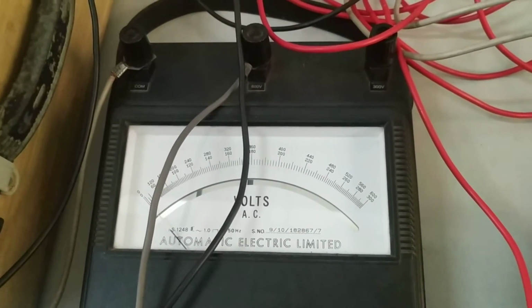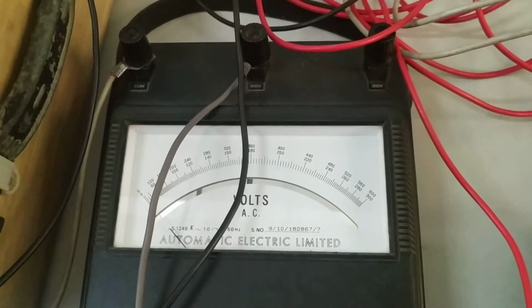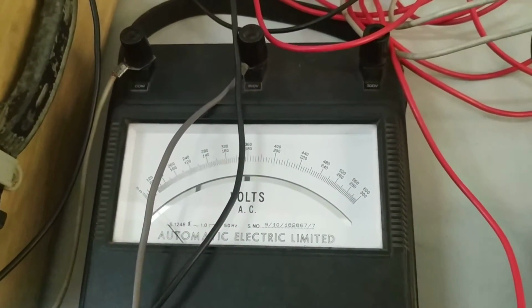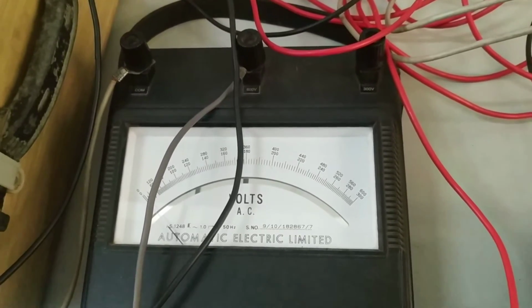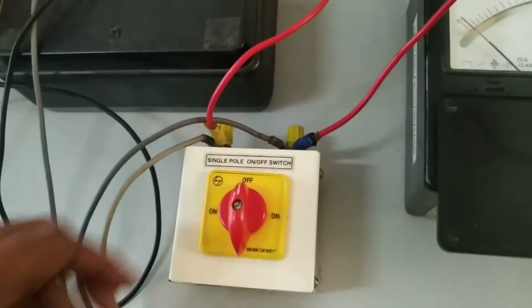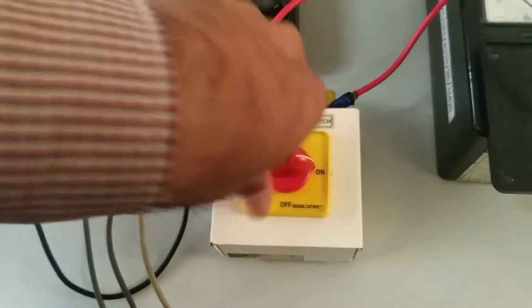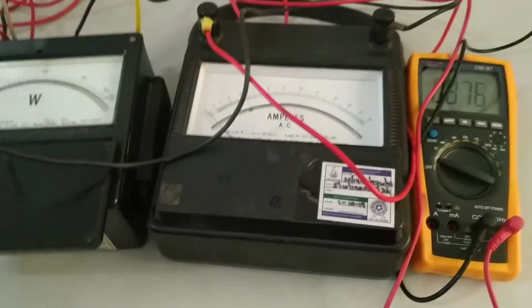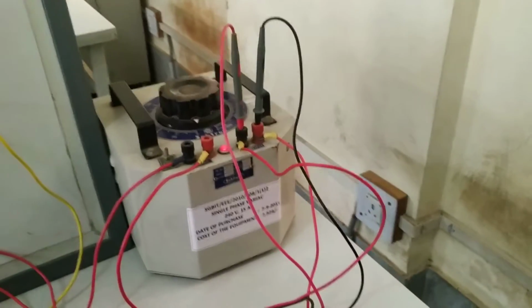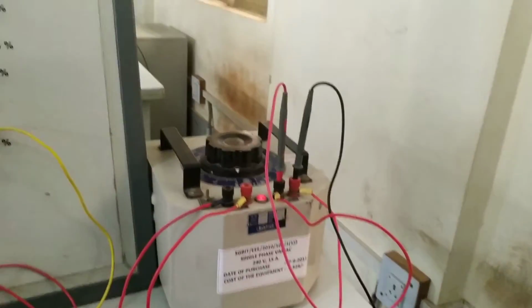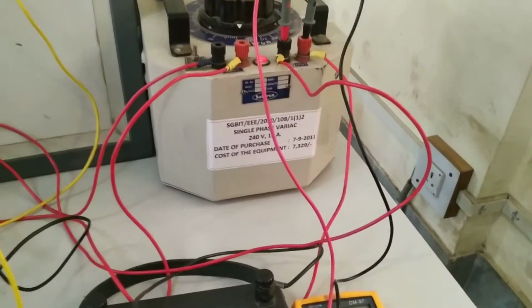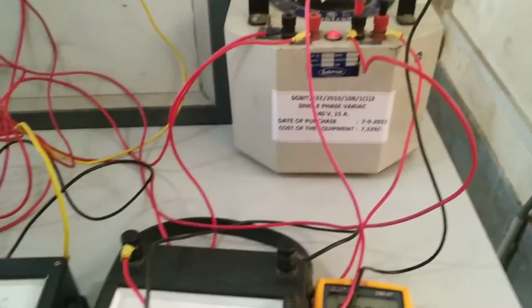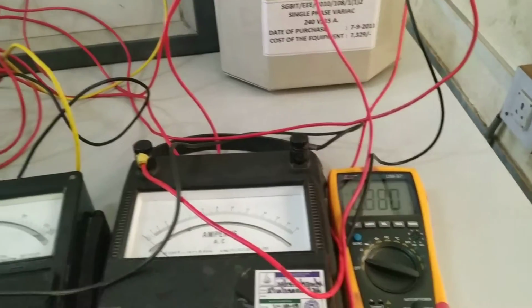At that time, the polarities of both the transformers are not the same. If it is showing 0, the polarities of the transformers are the same, and we can continue the procedure. Okay, now we can close the switch, and with the help of another auto transformer we need to apply the reduced voltage to the setup. But before that we need to have the rated current of the transformer.